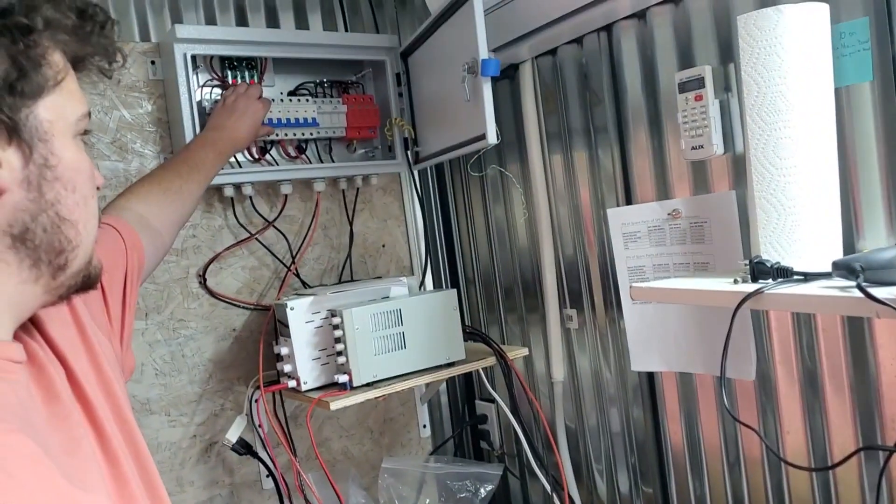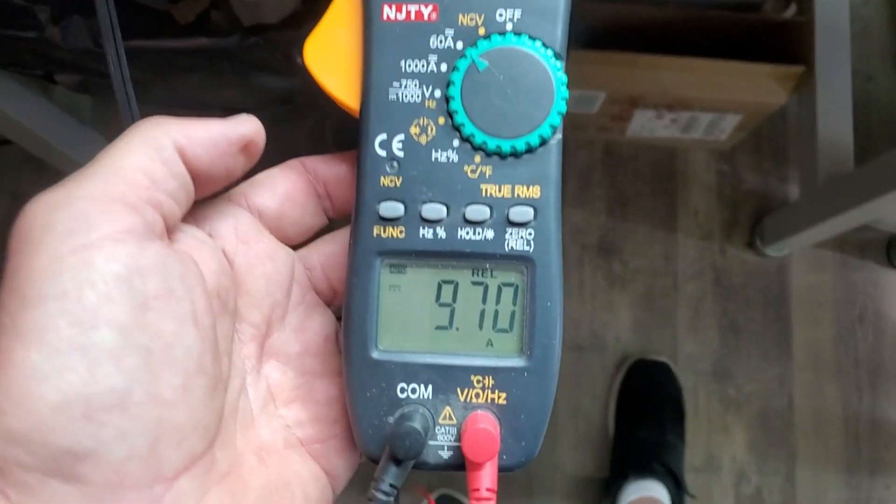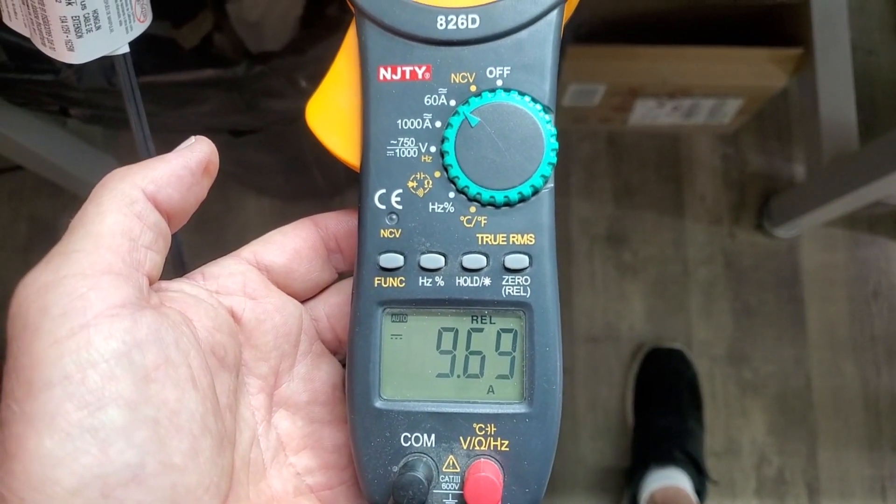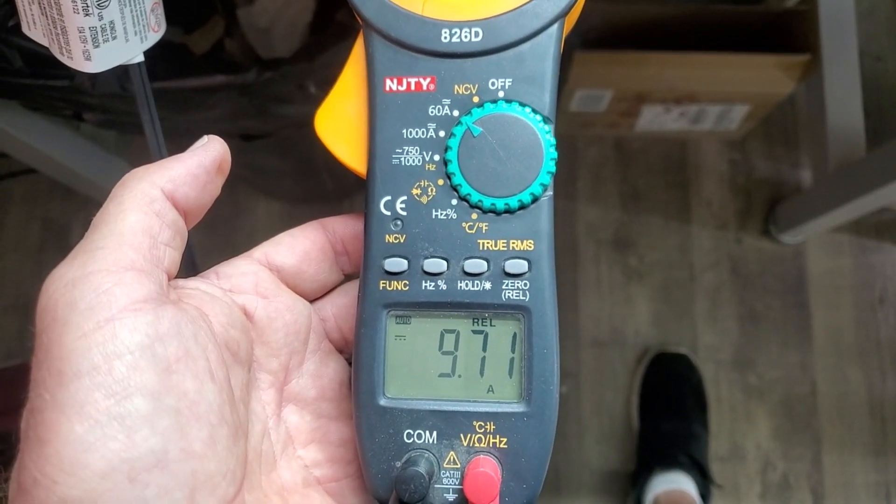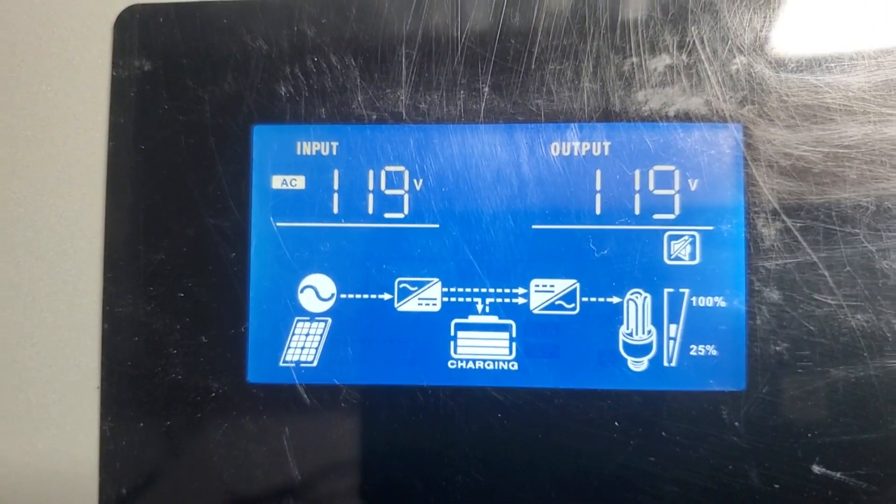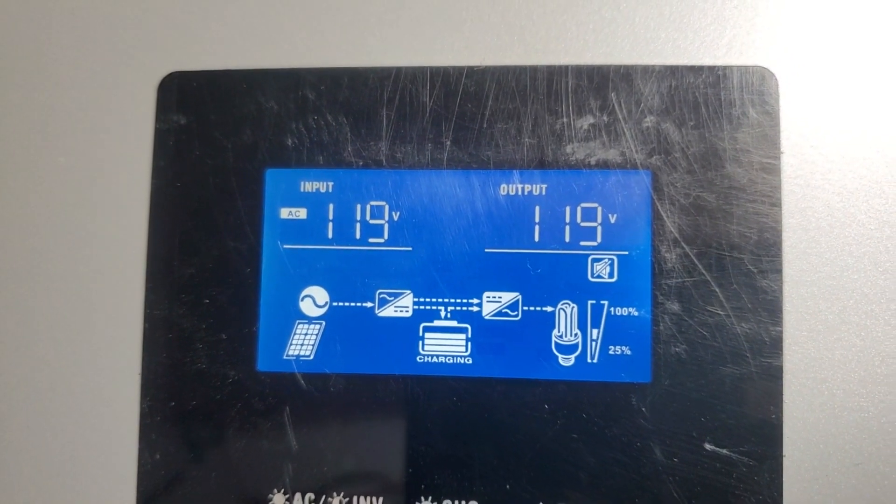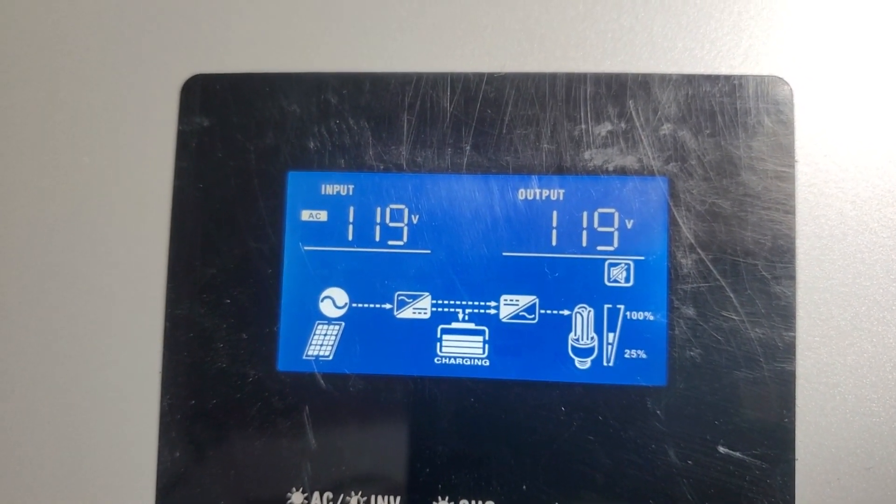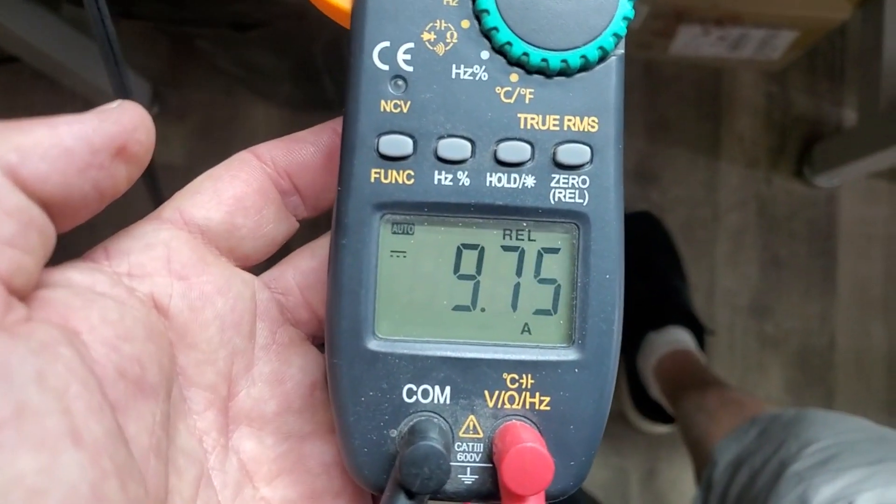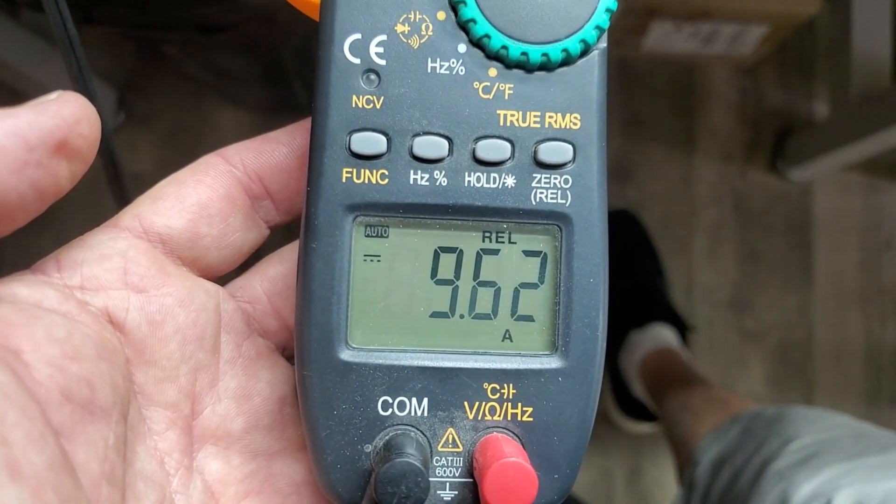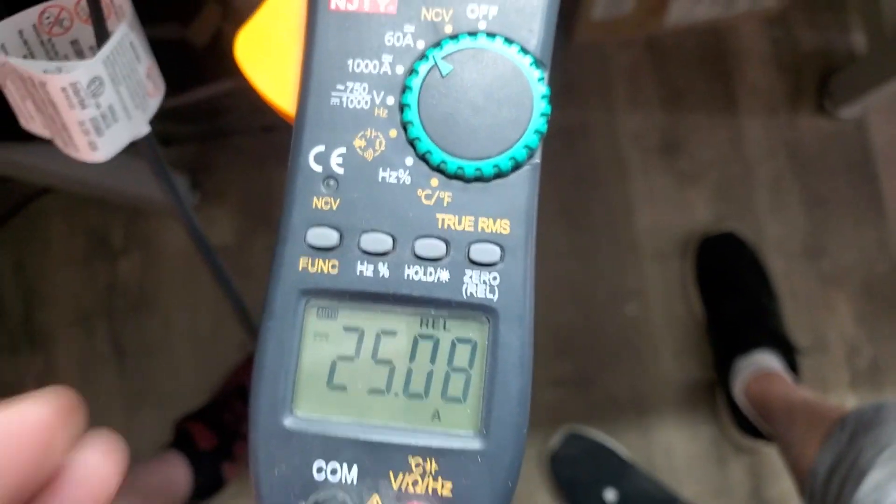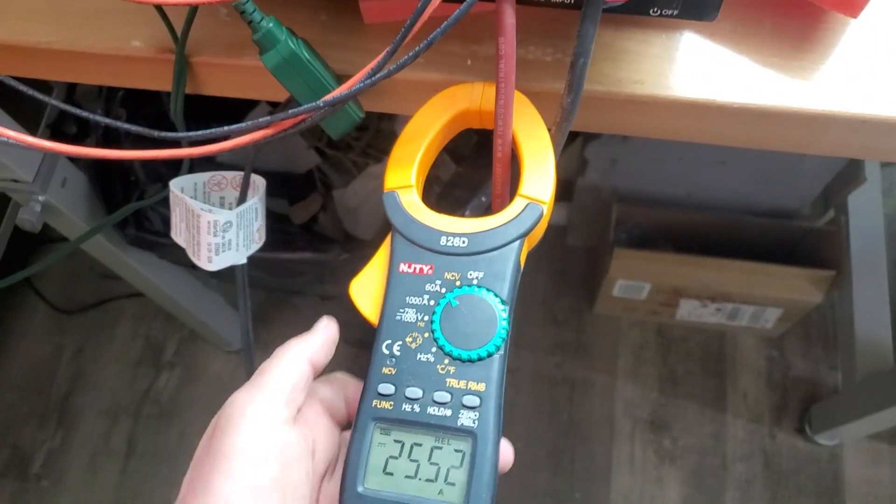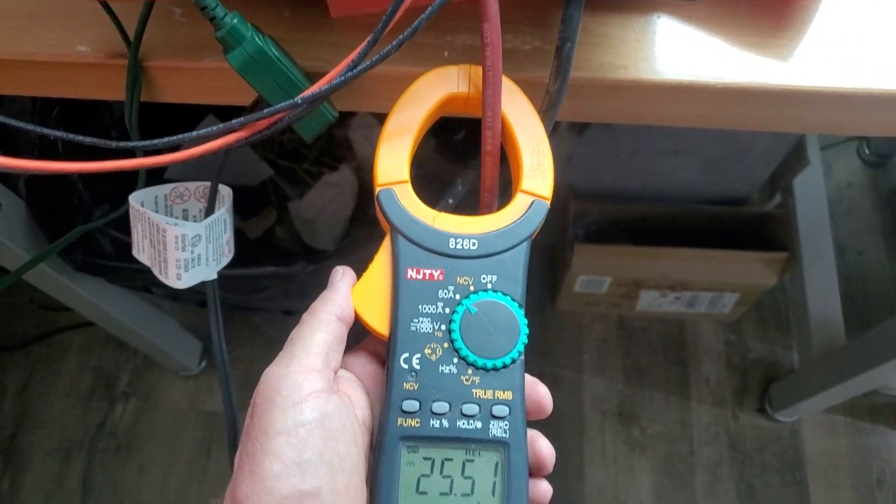So let's go ahead and turn the solar on. Let's flip them both up. And we'll notice that as the solar comes on, it should start charging the battery a little bit harder. And we'll notice there. So just barely showing the solar icon coming up. And there the solar is starting to power the load. And you'll notice that these amps now will start to climb. So now we can see our amps to the battery are at 25 amps with the solar connected. And the heat gun is still going strong in the back end.